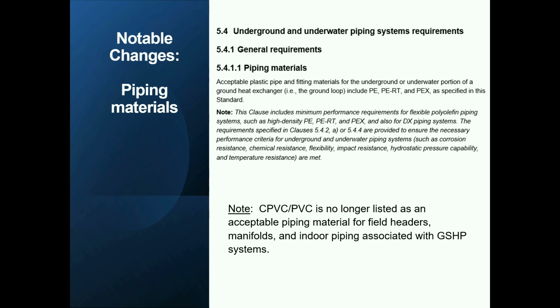Thanks, Greg. Some notable changes - as I mentioned, there were background committees that looked at different aspects, and one of them was the piping task force. One interesting change is that CPVC and PVC, to be standard compliant, will not be allowed as materials. Why? There have been a lot of studies done, and there are real issues with antifreeze agents and CPVC and PVC, the way they're put together, which is basically called chemical welding, but it's actually glue.